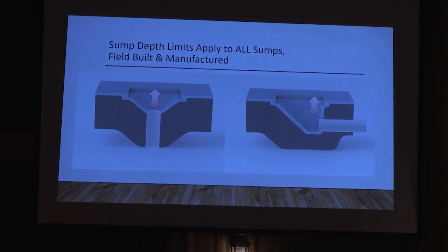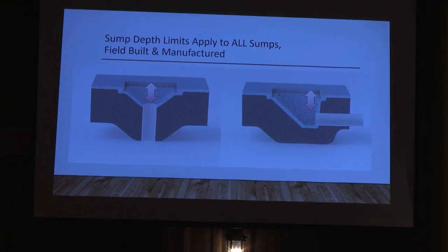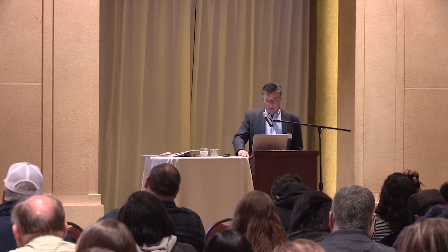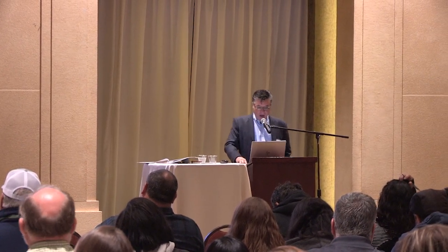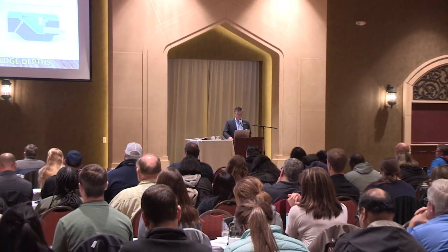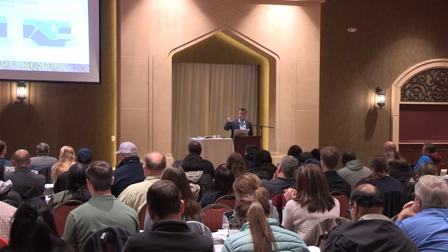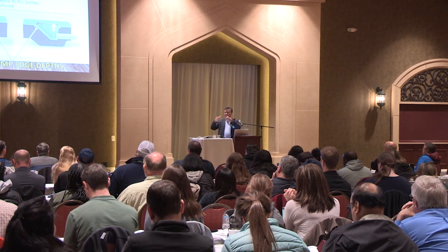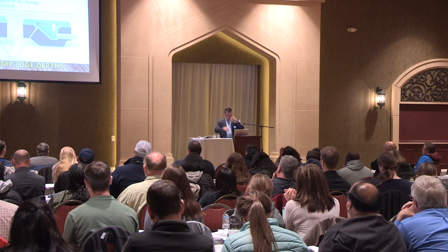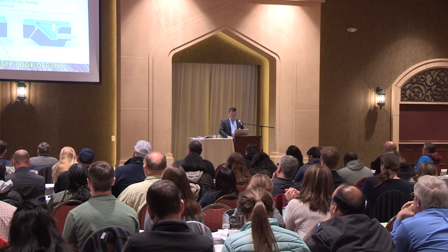Versus the current standard is to the underside of the cup. We didn't think through how do you measure that? So there's some room for improvement. So the sump depth is 1.5 pipe diameters, or as specified by the manufacturer. But here's something that I see a lot as a manufacturer, and that's where they got the pipe depth, but it comes, it's a plastic bucket that's round. Actually, let me do it the easy way. I'll show you.